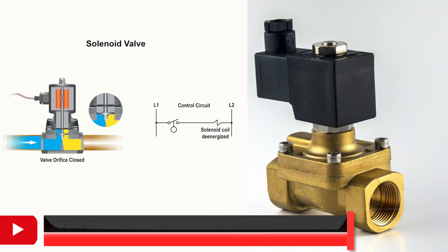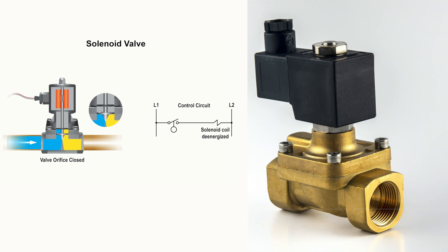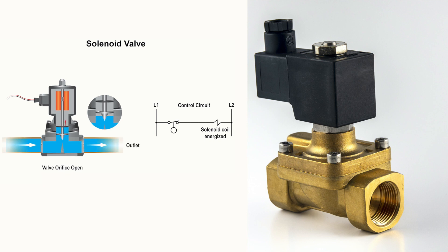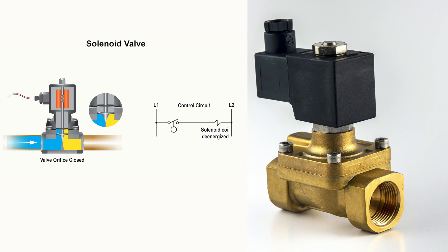The solenoid valve is an electromechanical valve consisting of the solenoid, coil, and a plunger that is connected to the stem of the valve. They are used to control the flow of liquid or gas in pipelines or certain processes. When current is passed through the coil, a magnetic flux is produced around the coil which allows the motion of the plunger. While being energized, it will either open or close to direct the flow of the substance. When current is removed, the magnetic flux is removed. Solenoid valves are commonly used in tank processes.